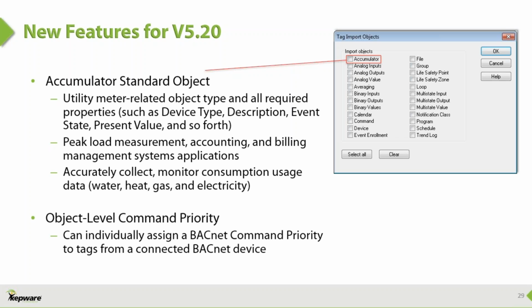Next, we spent a lot of time enhancing our command priority settings. Previous versions allowed only a single command priority to be used for all tags on a BACnet device, which are represented by BACnet objects. Now users have the ability to individually assign a BACnet command priority to tags for more complicated devices that may be aggregating several controllers that don't currently allow for direct BACnet communication. This essentially allows users to temporarily adjust the command priority of any commandable object in order to manage a non-standard operation such as maintenance or maybe an alarm condition.